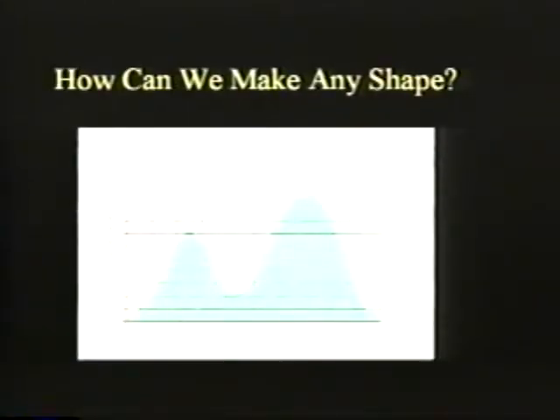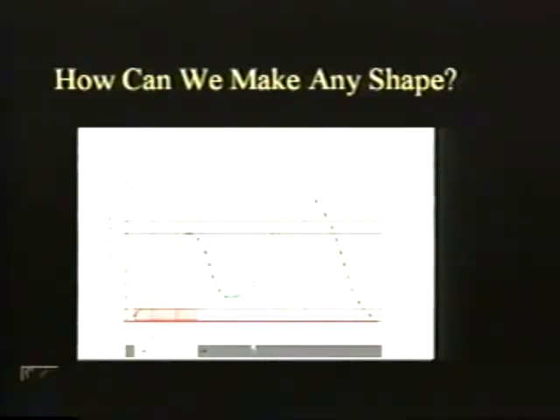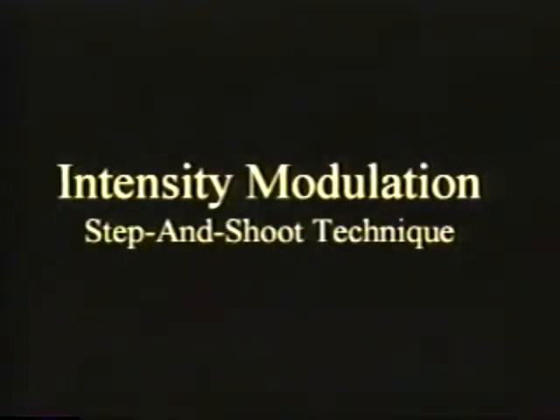How are we able to do this with the multi-leaf collimator? Here I've got a shape that we would like to make in radiation dose. Down here at the bottom I have the multi-leaf collimator leaves. And we've got a window between these two leaves. And it starts on one side of the field. The radiation beam turns on and deposits this red amount of dose. And then the leaves move on to the next position and deposit radiation dose in this next segment. And this is repeated by sliding this window from one side of the field to the other to make any three-dimensional dose shape. There are several different techniques for doing intensity modulation.